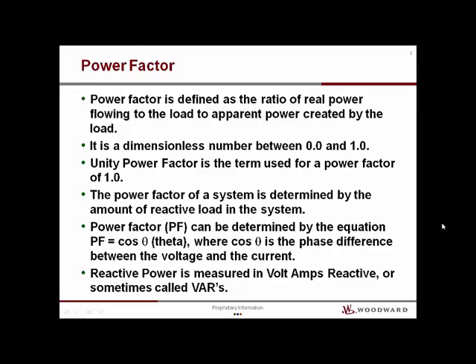Power factor is a dimensionless number, normally around 1.0. A power factor of exactly 1.0 is called unity power factor. The power factor of a system is determined by the amount of reactive load in the system. Power factor can be determined by the equation: power factor equals cosine theta, where theta is the phase angle difference between the voltage and the current. Volt amps reactive, or VARs, is the reactive power unit of measure.